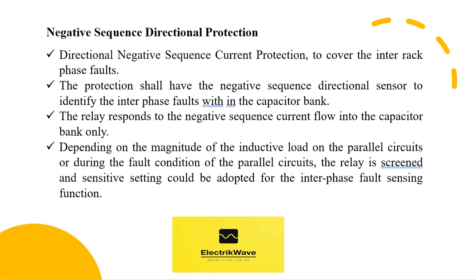Negative sequence directional protection shall have directional negative sequence current protection to cover the inter-rack phase faults. The protection shall have the negative sequence directional sensor to identify the inter-phase faults within the capacitor bank. The relay responds to the negative sequence current flow into the capacitor bank only. Depending on the magnitude of the inductive load on the parallel circuits or during fault conditions of the parallel circuits, the relay is screened and a sensitive setting could be adopted for the inter-phase fault sensing function.